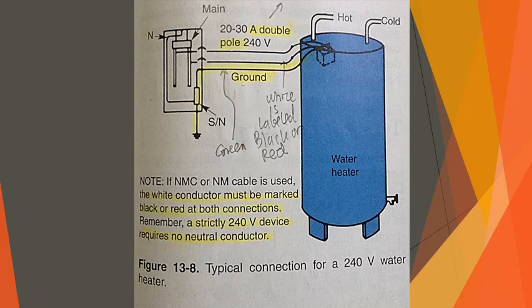A 20 amp circuit should be used for heaters up to 4 kilowatts, or 4 kVAs, while a 30 amp circuit is appropriate for those up to about 6 kilowatts, or 6 kVAs. These would be wired with a 12 AWG or 10 AWG conductor respectively. For this, see figure 13-8. This manner of connecting the water heater will provide 24-hour heating.